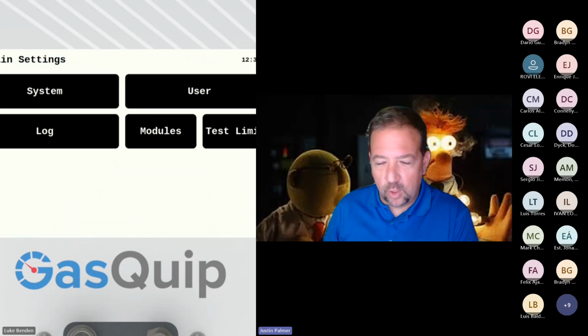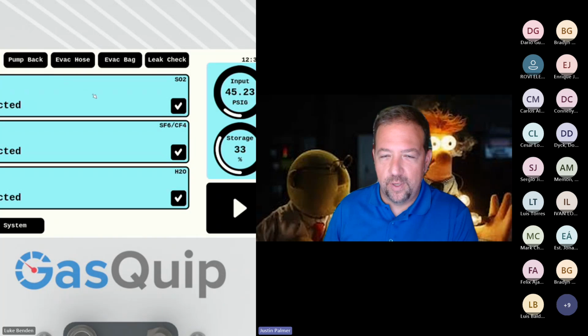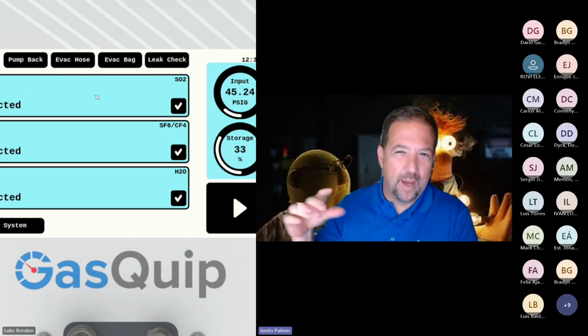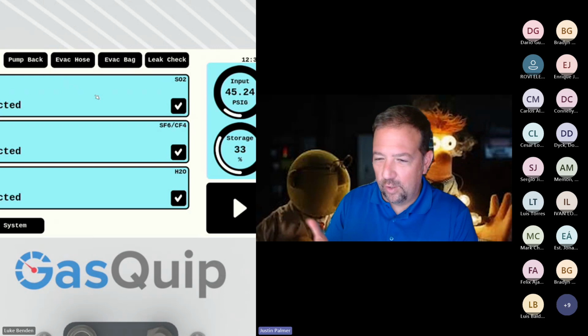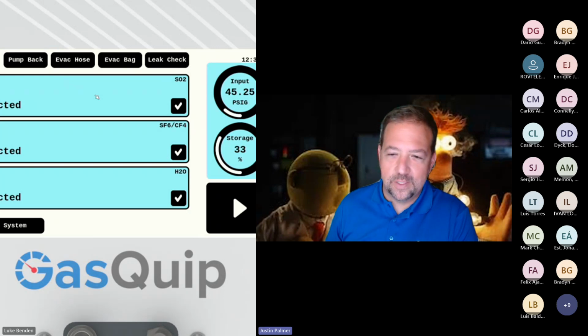Some companies run them a little bit over a year. They'll still work, but if you start looking at the margin of error you have, it gets pretty significant. So that's why we've kind of recommended doing it a little more frequently, because it's not a super expensive sensor to change out, and it's a safety deal. But the others, there's not really a shelf life on those. Hopefully that covers the questions on that.